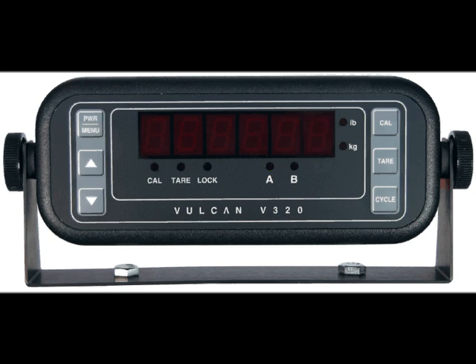There are two possible problems that may require service. If the meter display does not turn on during the truck's normal operation, press the power menu key. If the meter still has a blank display, notify the scale technician for service. If there is an error number code displayed, noted by the letters ERR, notify the scale technician for service.